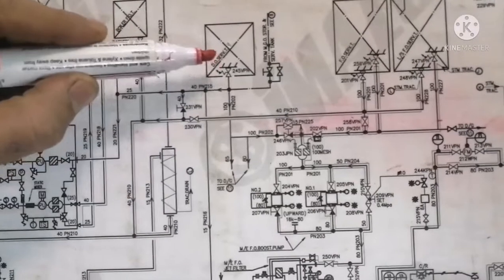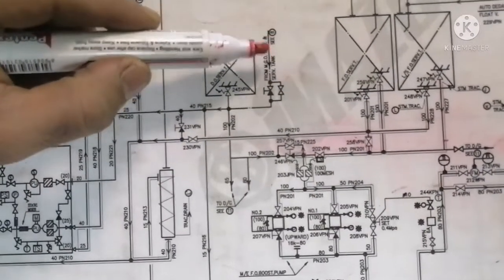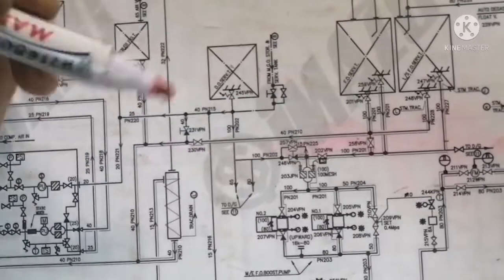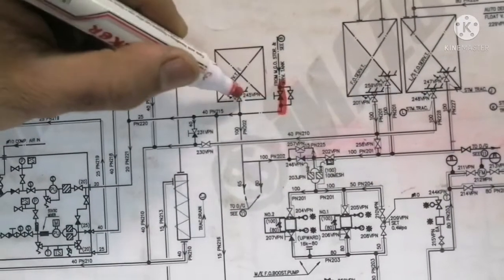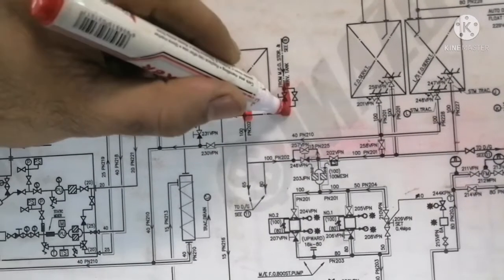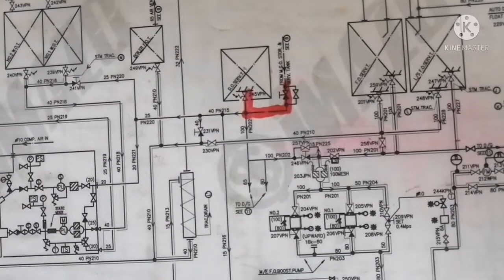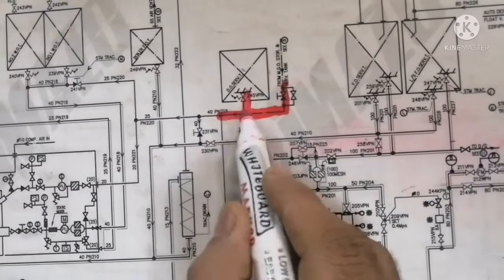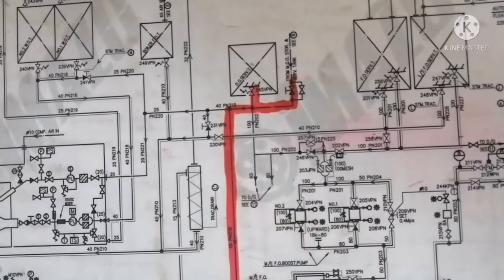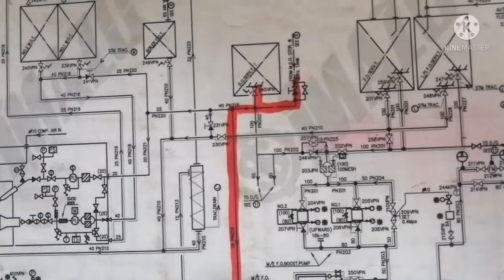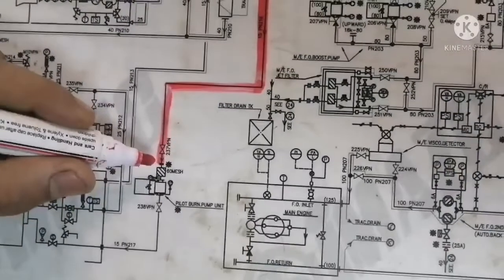This is your diesel oil service tank and this is your MGO storage tank. The line comes from the outlet here — these two are connected. Once they are connected, it goes all the way down, and you can see a filter over here — this is your 60-micron mesh filter.